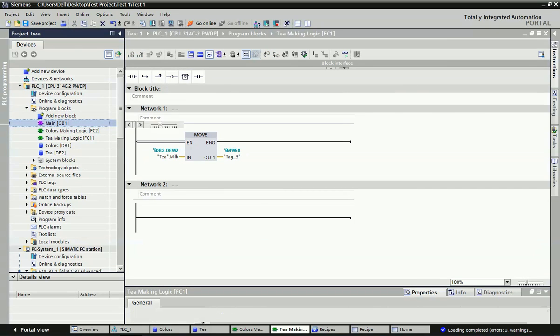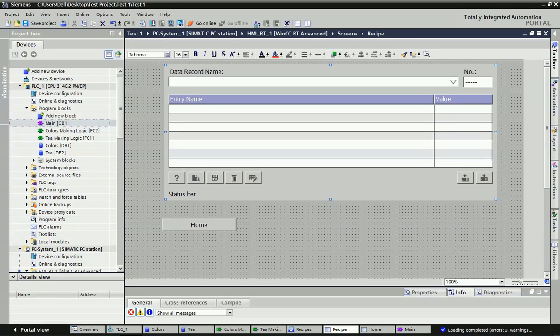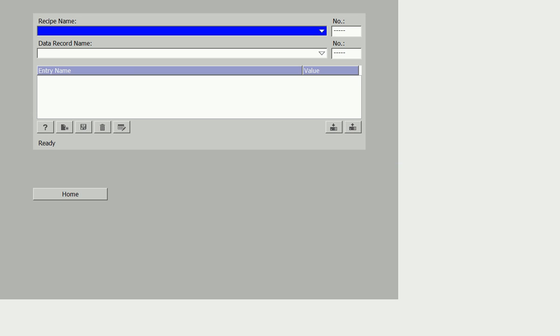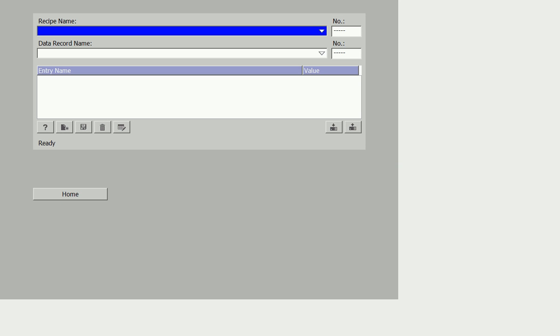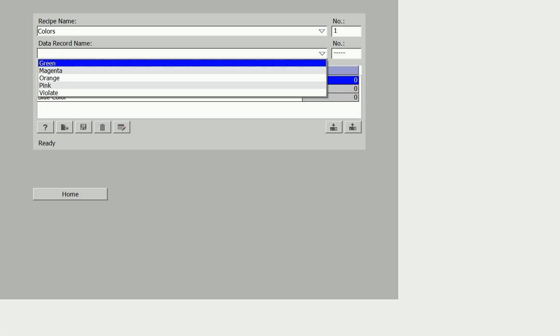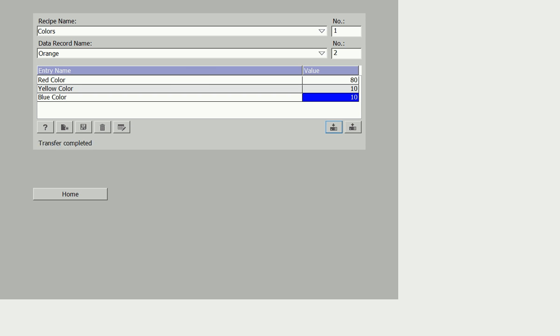Now we will download this logic to the PLC. From SCADA we will go to runtime by clicking the Runtime button. We will switch to Recipe View. In the recipe view, you can get the recipe name. I will select the recipe name and data record - for example, the orange color. You can see on the lower side the red, yellow, and blue concentration values appear automatically. You can click and change the value. After changing the value, just click the Download button so this value will be downloaded to the PLC. You can see the 'Transfer Completed' message. You can also save this data record.